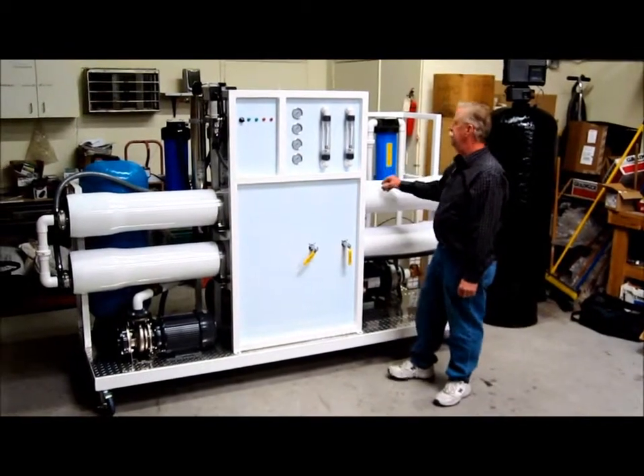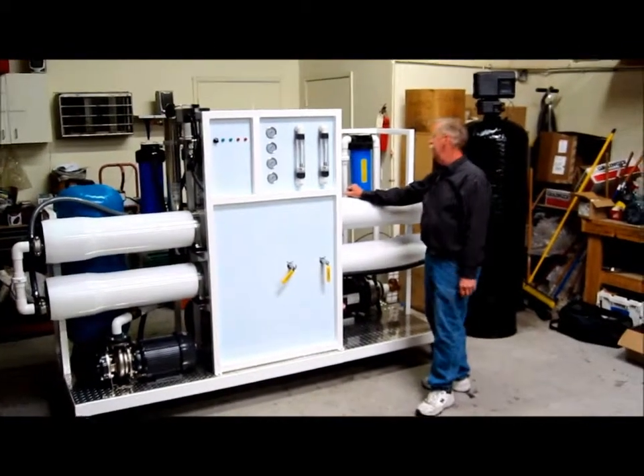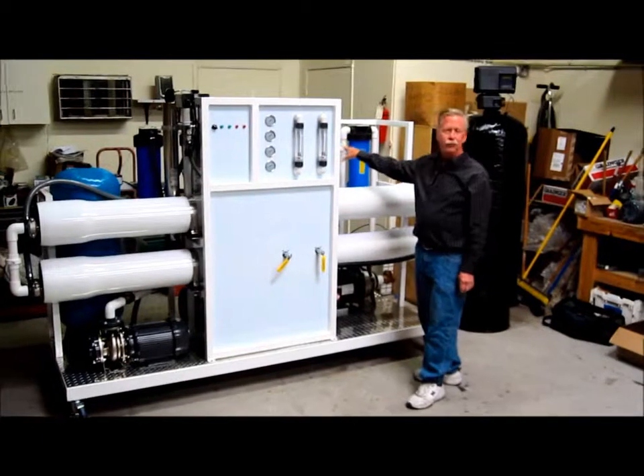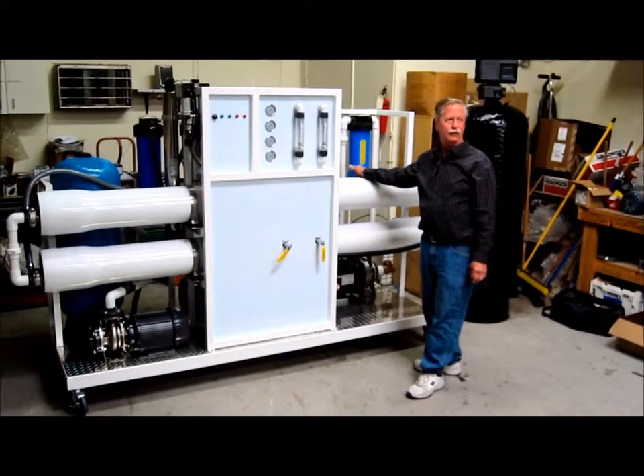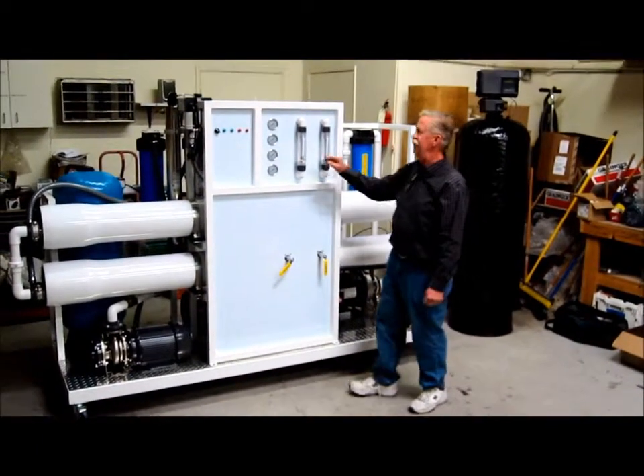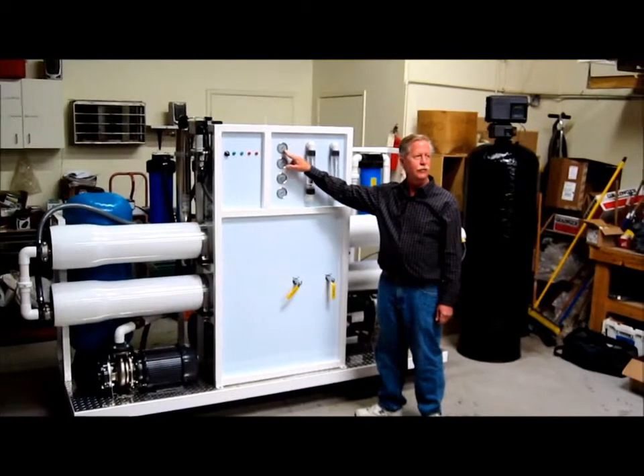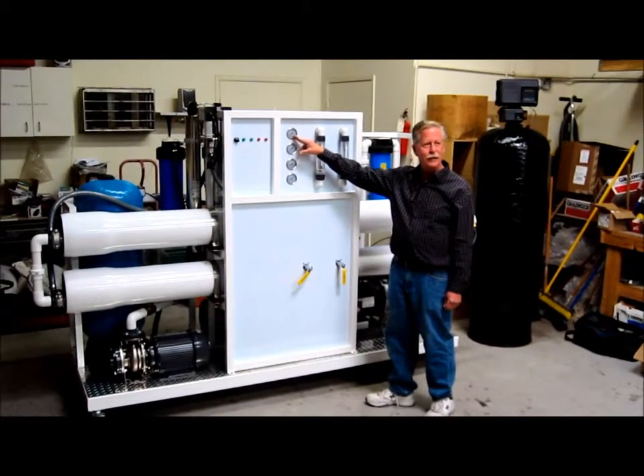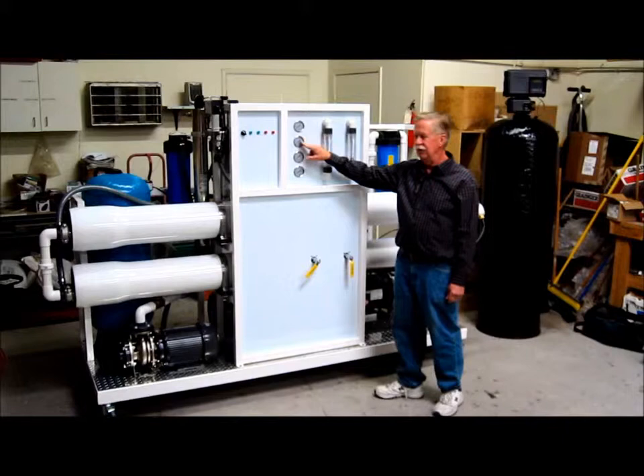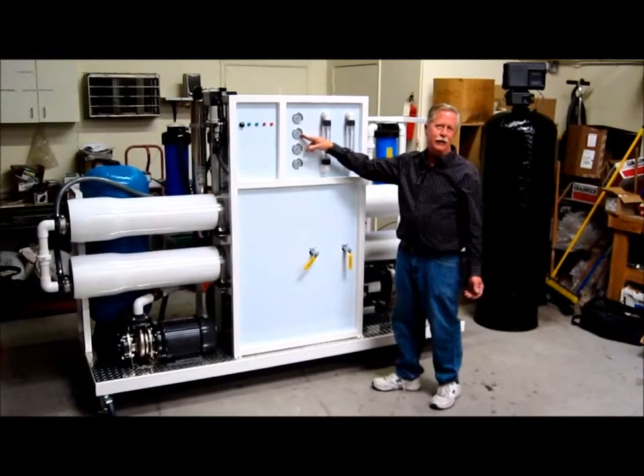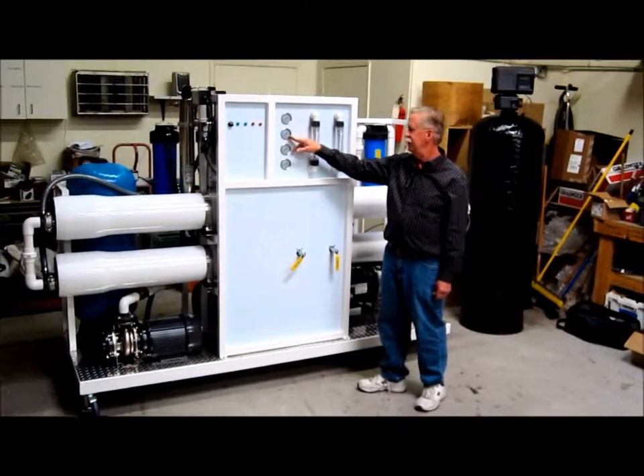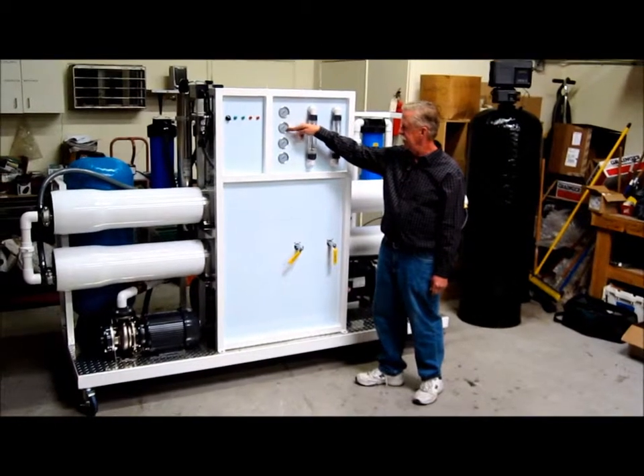Now, as mentioned before, we have pre-filters on here. When these pre-filters get dirty, the flow starts going down and you can get a pressure drop. So this gauge tells you the pre-filter pressure going into the filter, and this tells you going out. So when you have an 8 to 10 pound pressure drop, you know it's time to change those pre-filters.